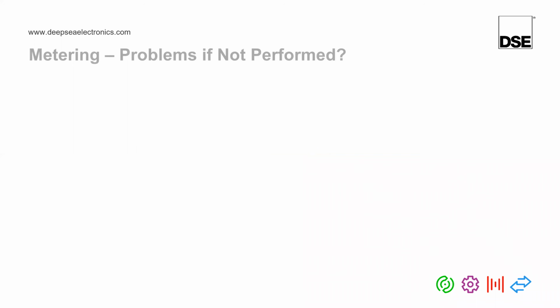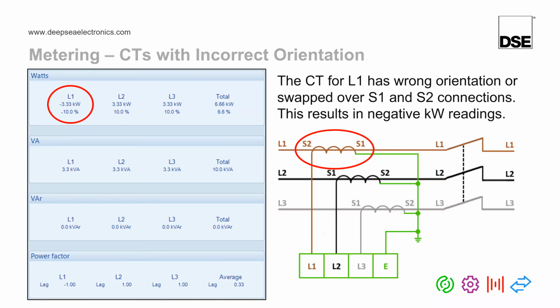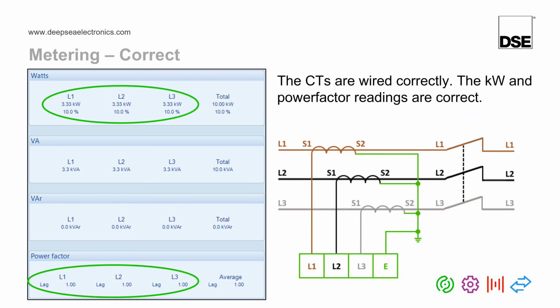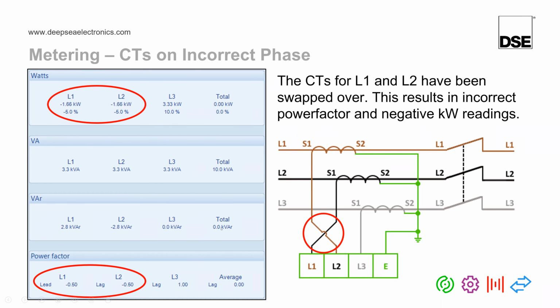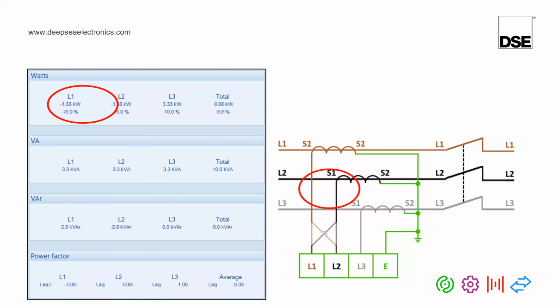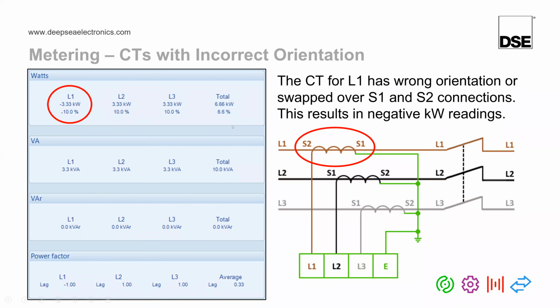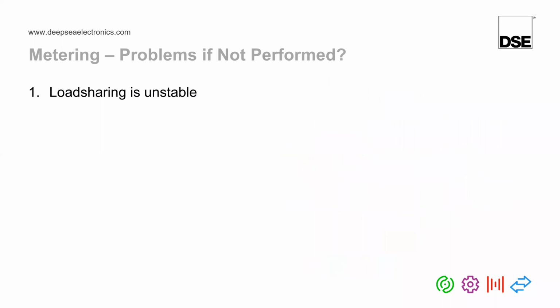So what happens if we don't perform these tests? Well, again, you will end up having unstable load sharing, because going back to the previous slides, if we look at what was wired correctly, here you can see that we should have 10 kilowatts and no VARs. Looking at the first problem, we supposedly now have 0 kilowatts and 0 VARs. So we're reading power completely incorrectly on this generator. Or in this example, we have 0 VARs, but a lot less kilowatts. If the DeepSea module cannot measure the power correctly, it will not know how to load share correctly, and if it does not know how to load share correctly, your load sharing is going to be unstable.